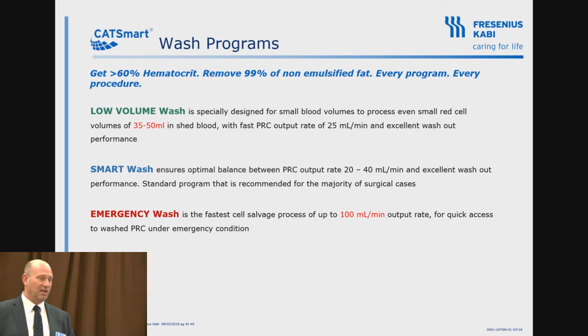And each one of these programs gets out 100% or 99% of the fat. I'm going to show you the data on the emergency wash. Smart wash, super washout rates. Low volume wash is optimized for lower volumes coming into the chamber. It kicks in a little sooner. It's a little slower, but you can then optimize red cell salvage for like pediatrics or ortho or something.